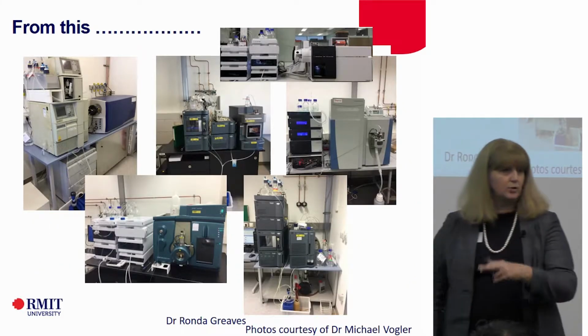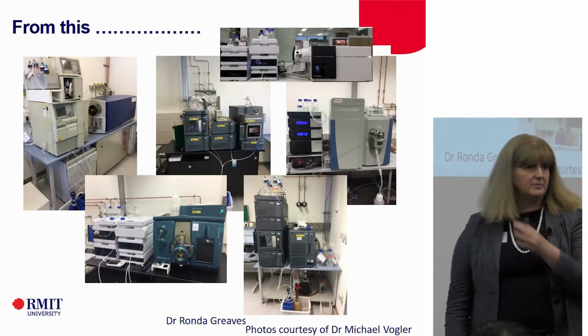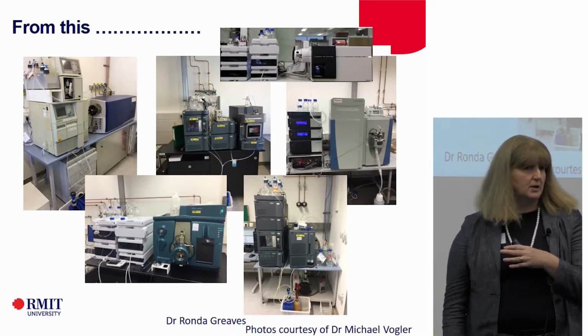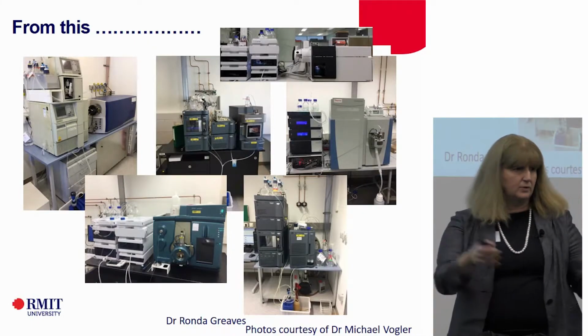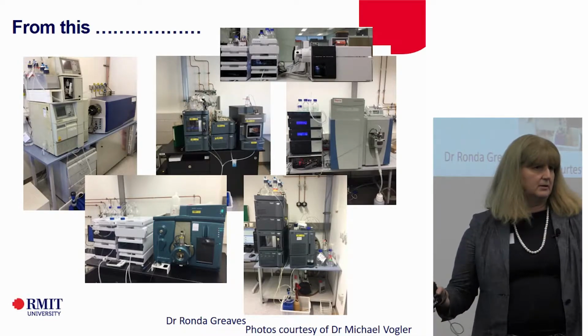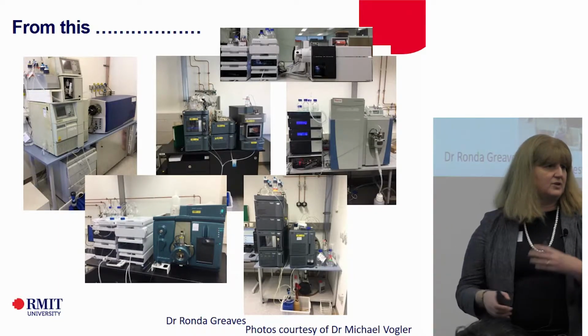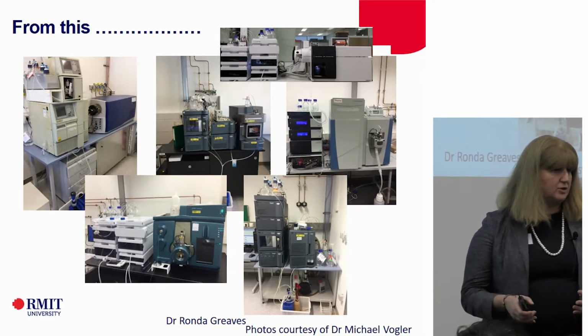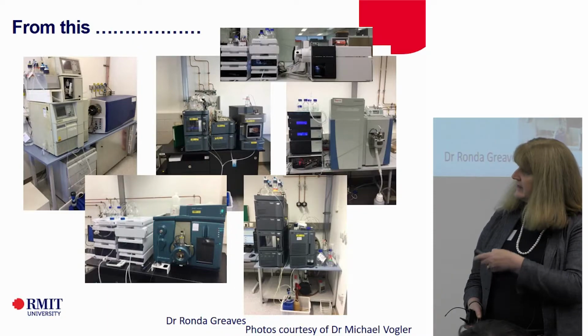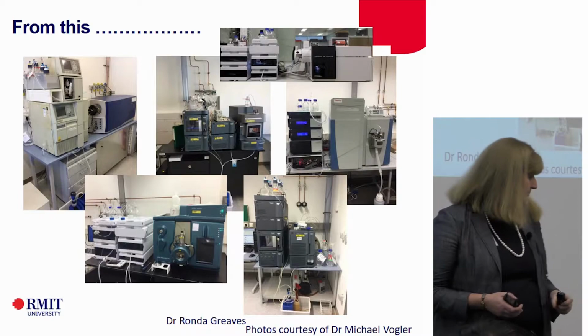I think this is our next problem, and I'm on my way to finishing now. We've got a bit of a mess with our mass specs. We do these hybrid approaches, so I don't think we can easily totally transfer one method to another. We've got different lengths of tubing, if I go down to something really simple. So we're going to have differences in retention time and slight changes in gradients and so forth. And I think we really need to work on this approach and how we can do this.